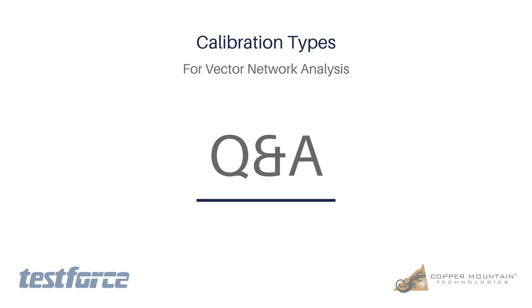And we have two more questions that came in at this point. I think we should answer those two and then maybe move back to the presentation because we're running a little short on time. You guys have all had great questions and we'll have another break shortly. The first one is how much of a change of temperature affects the calibration? 0.02 dB per degree C.